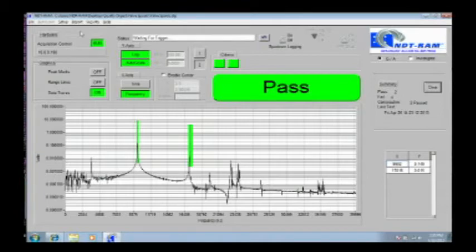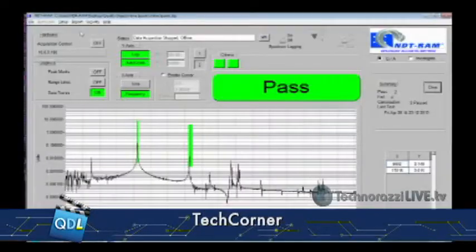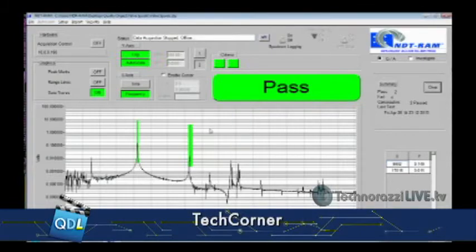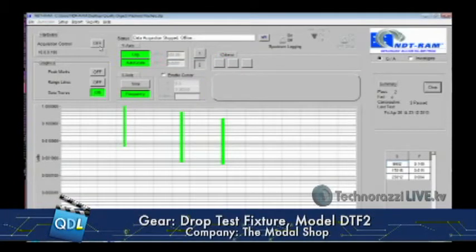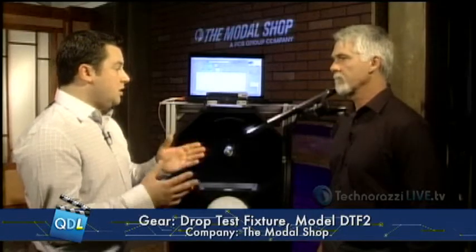So what we were looking at there was a cracked part. We also have a heat treated part. To switch to a different part, all I have to do is stop the program and load the file for the other one — we've already established what is a known good part on this. How do you train it to recognize a good part? We would typically run through several hundred known good parts that have passed a separate inspection, teach it, and overlay that data to look for differences between the known good and the known bad.